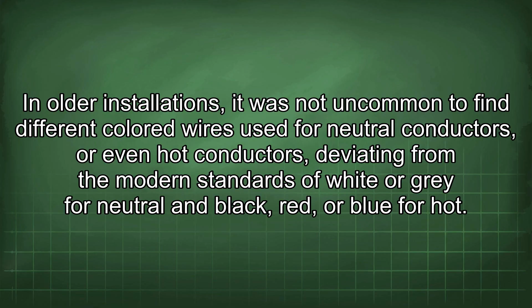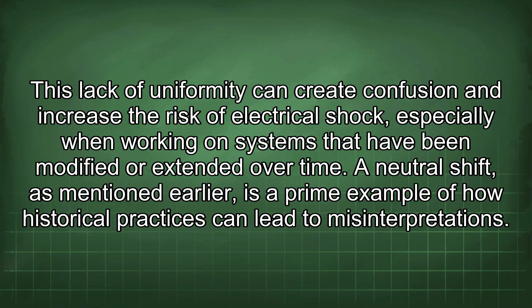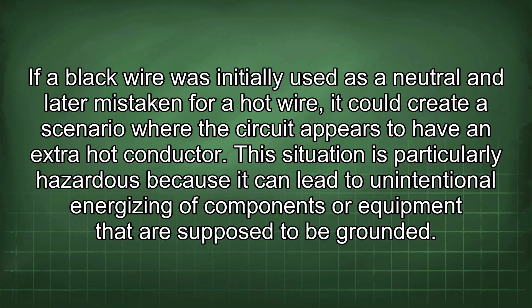This lack of uniformity can create confusion and increase the risk of electrical shock, especially when working on systems that have been modified or extended over time. A neutral shift, as mentioned earlier, is a prime example of how historical practices can lead to misinterpretations. If a black wire was initially used as a neutral and later mistaken for a hot wire, it could create a scenario where the circuit appears to have an extra hot conductor. This situation is particularly hazardous because it can lead to unintentional energizing of components or equipment that are supposed to be grounded. The possibility of a factory wiring error should not be overlooked.